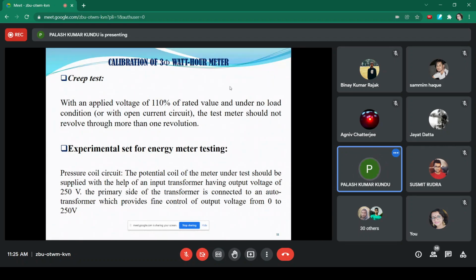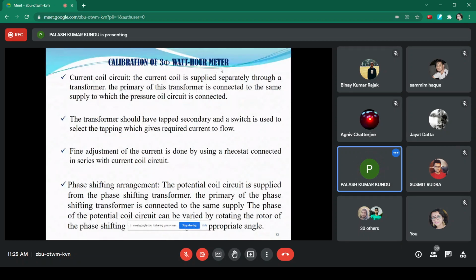Now, what is the testing circuit? What is the experimental setup for energy meter testing? It is called the phantom loading circuit. That means two separate power supplies are used: one to excite the current coil of the energy meter, another to energize the potential coil or the shunt magnet. And there must be a phase shifting arrangement so that different power factors can be made. So a phase angle difference should be produced by the phase shifting arrangement. These are the conditions of phantom loading.